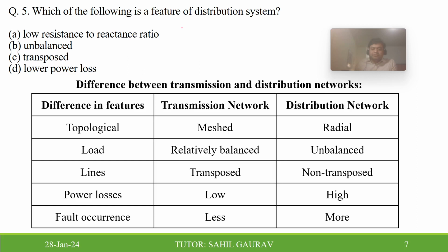So the R/X ratio is very high in the case of a distribution system. The first one is incorrect. And the second option is unbalanced. Yeah, it is unbalanced in nature. You can see from the table also. Distribution networks are unbalanced in nature while transmission networks are relatively balanced. So this is the correct feature. And transposed: we do transposition of lines for transmission, not in the distribution line. So it is also incorrect. And lower power loss is also incorrect because it has a high R/X ratio. That's why it has higher power loss.